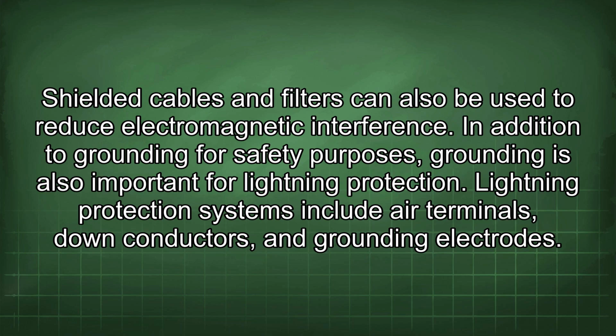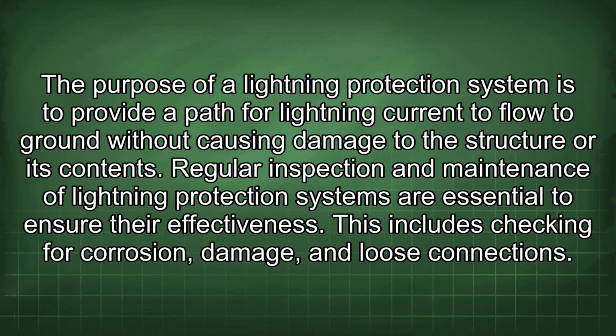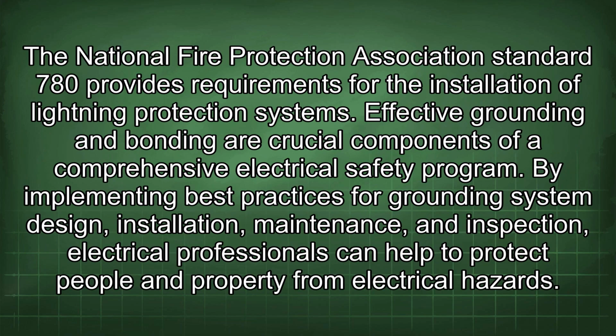In addition to grounding for safety purposes, grounding is also important for lightning protection. Lightning protection systems include air terminals, down conductors, and grounding electrodes. The purpose of a lightning protection system is to provide a path for lightning current to flow to ground without causing damage to the structure or its contents. Regular inspection and maintenance of lightning protection systems are essential to ensure their effectiveness. This includes checking for corrosion, damage, and loose connections. The National Fire Protection Association Standard 780 provides requirements for the installation of lightning protection systems.